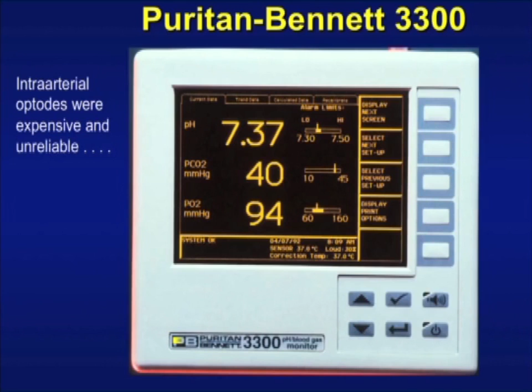Cost cutting, cost consciousness. There were two problems with intra-arterial optodes, and I was very aware of and very frustrated by these problems. They didn't always work as beautifully as that case I just showed you. When you put a foreign body in the blood, the blood doesn't like that. It wants to coat it with fibrin and platelets and basically schmutz and cover it up and protect the body from it. So they were unreliable, and in fact in a lot of patients, the Optodes simply didn't give reliable readings at all. They were also expensive. They could not get the cost of the disposable part down below about $300. That in the early 90s was a lot. As a result, you see what happened down here. Puritan-Bennett is no more. It was absorbed by Nellcor, which was eventually absorbed by Tyco, and the cycle goes on.